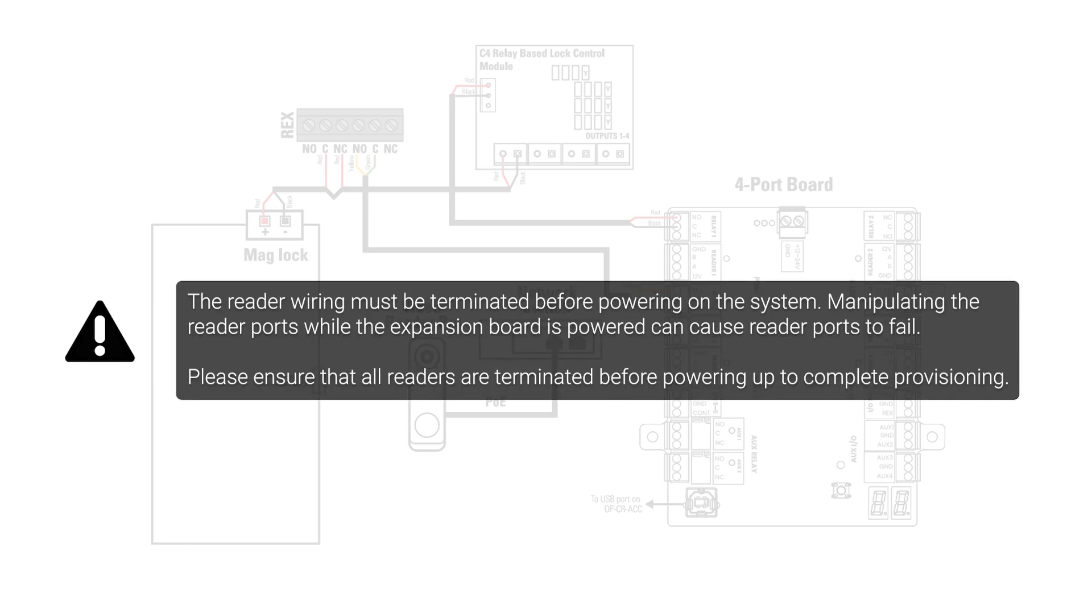The reader wiring must be terminated before powering on the system. Manipulating the reader ports while the expansion board is powered can cause reader ports to fail. Please ensure that all readers are terminated before powering up to complete provisioning.